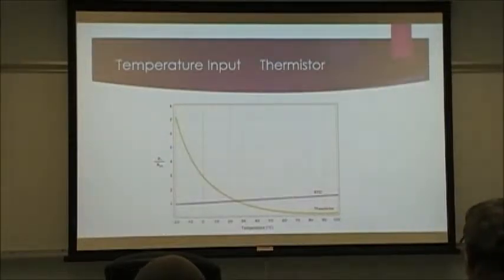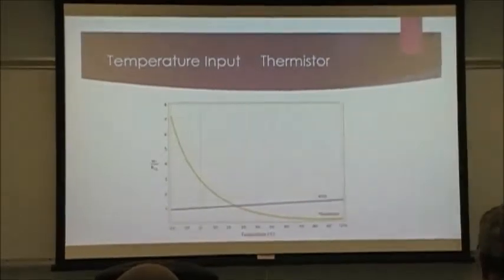And basically, you can see it changes. And these are units of resistance right here, 0 to 7.25. And this is temperature from -20 to 100. You can see that our thermistor has a very sharp curve on it, okay? Now, the controller is programmed to look at that curve. The RTD has a very shallow curve. Typically, they use these on scientific equipment, and they're very accurate within a very short range, okay? So there's a purpose for them.